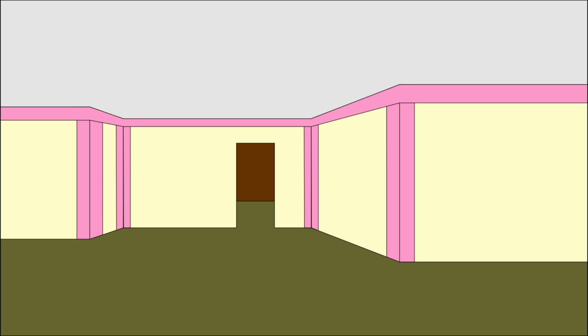So in summary then, before you even started putting electrical equipment in, you've already got all of these pink areas here where you can install cables. So there's a strip around the top against the ceiling, and that's 150mm wide. And then you've also got anywhere where there's a corner, so it's an internal or external corner. Again, those are 150mm wide on each of the walls, so the whole zone there is effectively 300mm wide. That's about 12 inches. And so that's for any cables you want to put there.